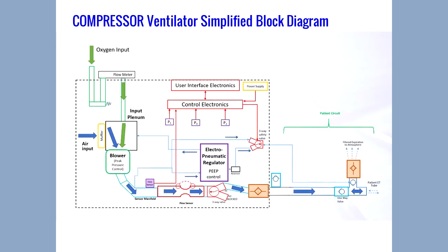The compressor design has a motor. It has a blower, and it takes in ambient air. Oxygen is again flowing in under pressure, and then there is one input plenum that is used to manage both the low and the high pressure that the patient needs, both inhaling and exhaling. So it's one pressurized chamber that is used for both situations, so the control is a little bit more complicated. The two pressure chambers are not disjoint, they're one, and the pressure needs to switch between the high and the low. So the control electronics are a little bit more complicated, but it still works very nicely.